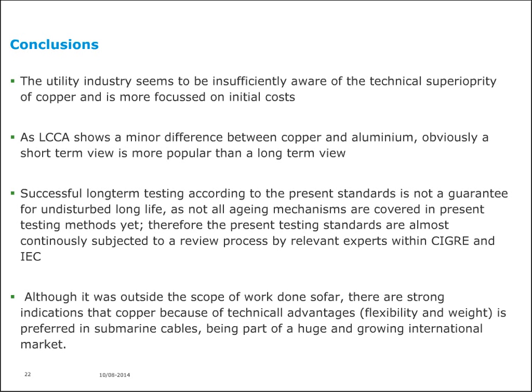May I give the example of water treeing? Water treeing was discovered in the 70s and 80s of the last century, and it was absolutely, completely unknown. Nobody ever thought that this would be a threatening mechanism, that water in combination with electric stress could result in so many failures. But it happened, and now all cables are tested to check if they are resistant to water tree formation or not.